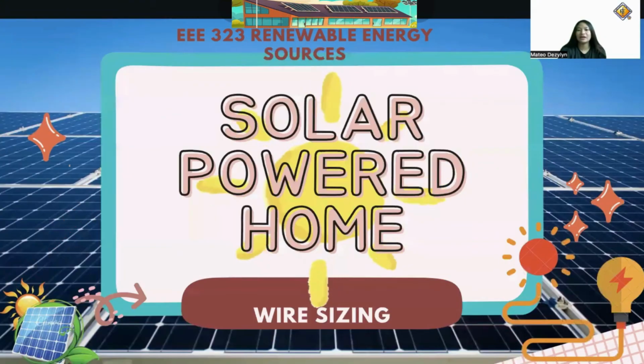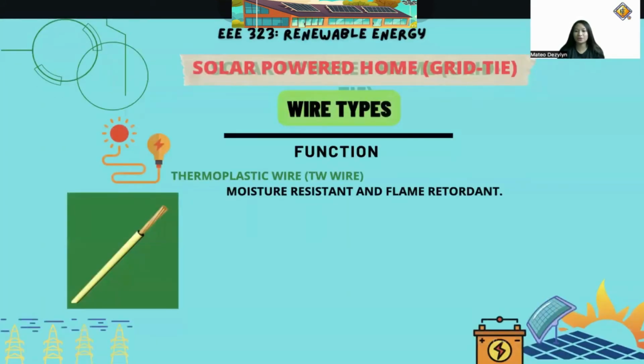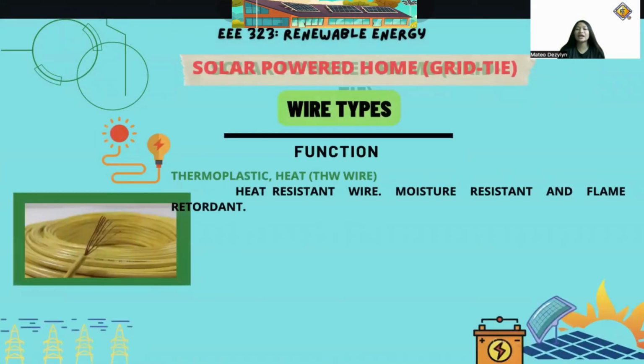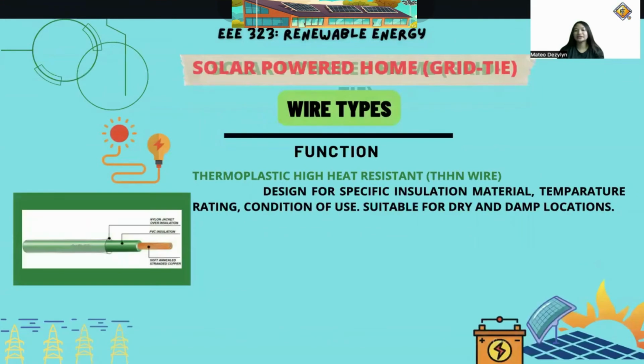Next is the wire sizing. The first wire is TW, or the thermoplastic wire, which is moisture resistant and flame retardant. Next is THW, or thermoplastic heat wire, which is heat resistant and also moisture resistant and flame retardant. And the next wire is THHN, which is highly heat resistant, designed for a specific insulation material, temperature rating, and condition of use, suitable for dry and damp locations.